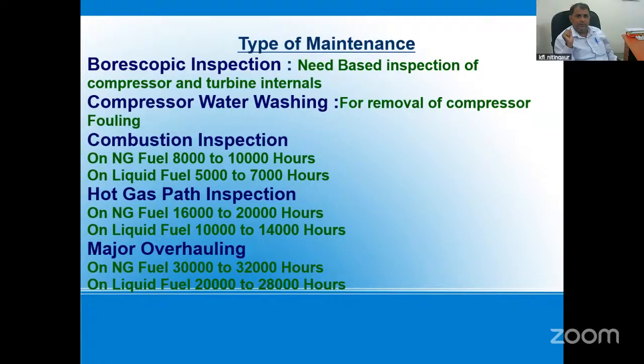And if your machine completes 16,000 to 20,000 running hours, this is not standby, this is running hours, then hot gas path inspection. Hot gas path inspection includes the combustion inspection and the area where the hot gas passes, means from the combustion area to the exhaust section. All the parts should be inspected very carefully because reliability of the gas turbine is a must, as all the plants depend on its power.